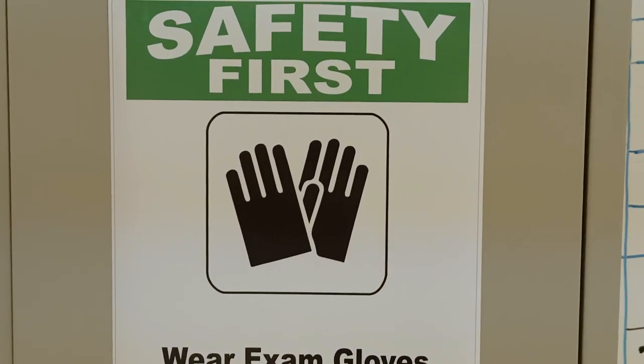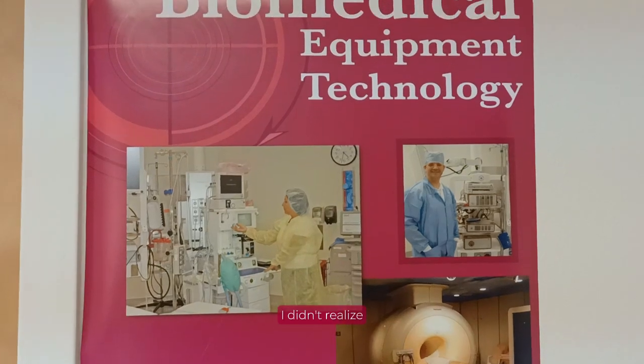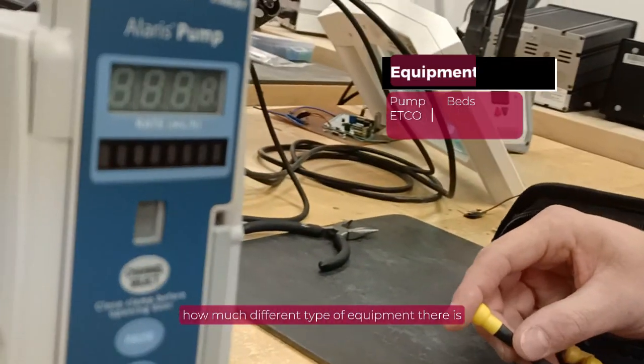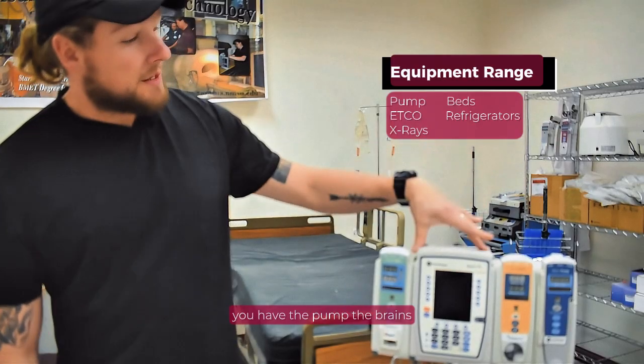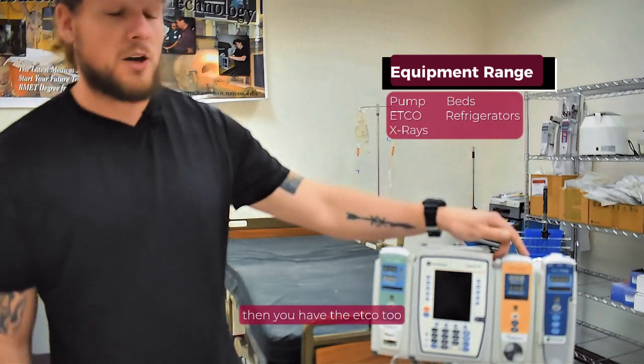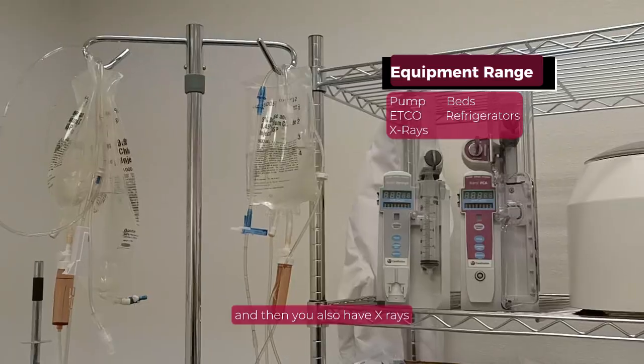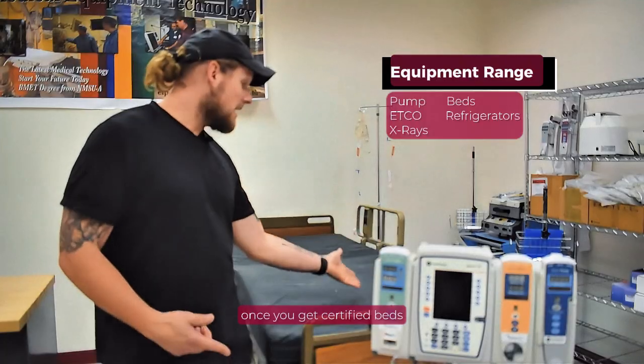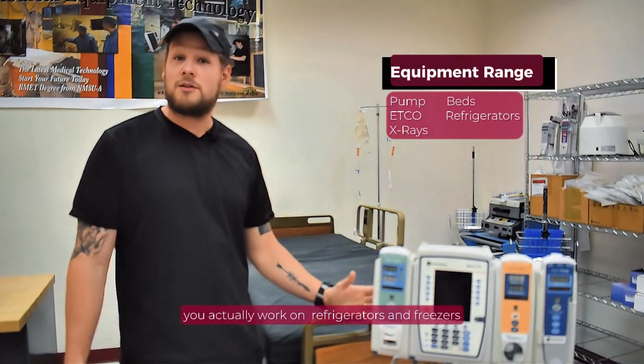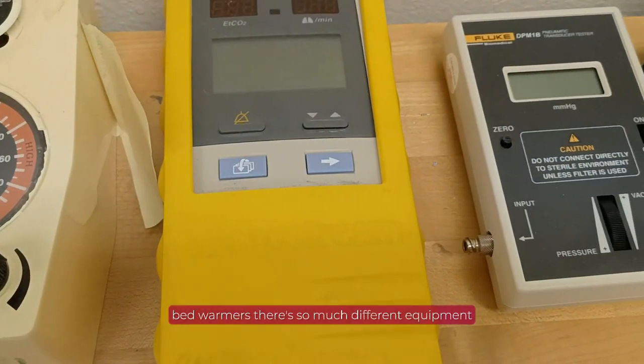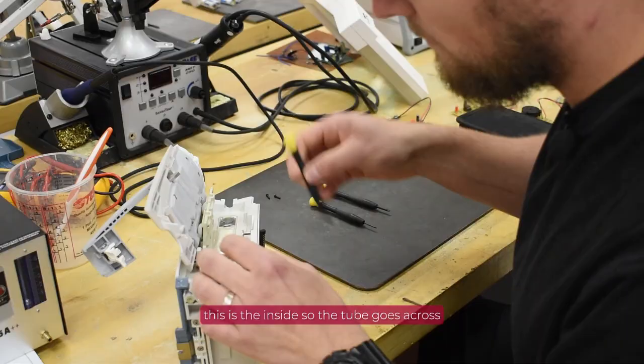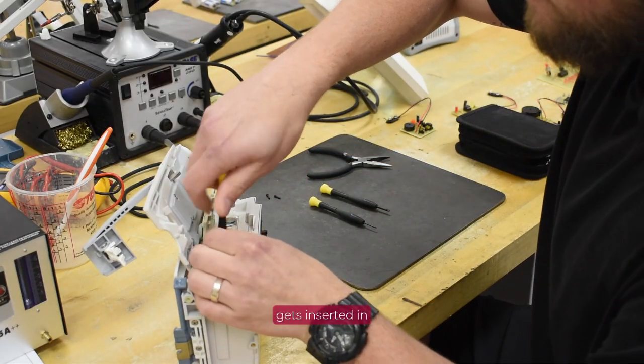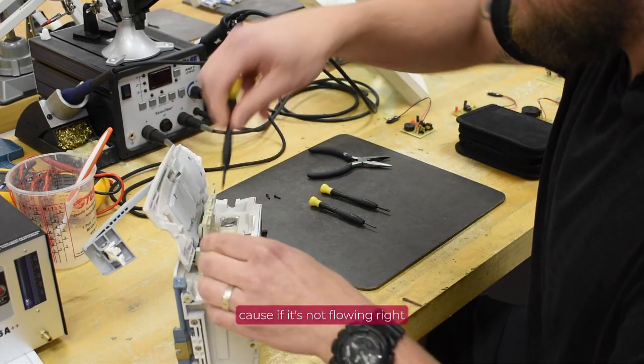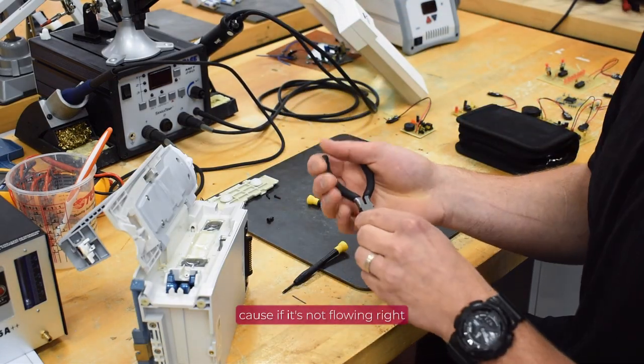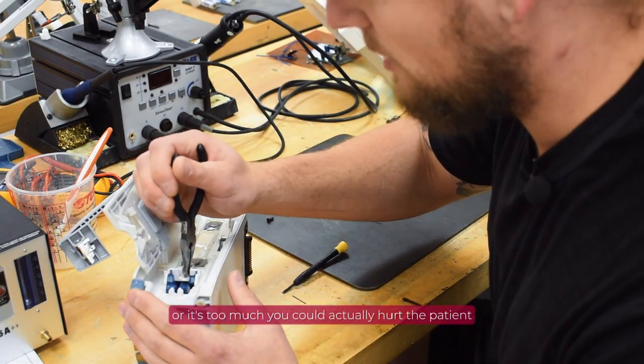When I did my internship at the hospital, I didn't realize how many different types of equipment there are. You have the pump, the brains, then you have the EtCO2, and then you also have x-rays once you get certified, beds, you actually work on refrigerators and freezers too at the hospital, bed warmers, there's so many different types of equipment. This is the inside, so the tube goes across, gets inserted in. You have to replace the sensor because if it's not flowing right or it's too much, you could actually hurt the patient. So this is the sensor that you have to replace.